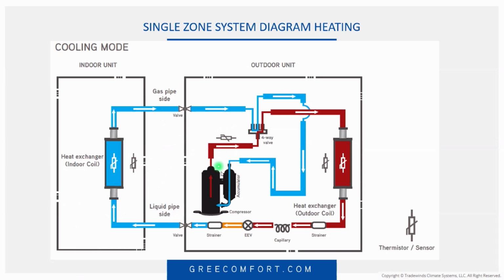That's one thing I really like about GREE. GREE is consistent in that they use a 50K thermistor for the discharge pipe. They use 20K thermistors for coil, whether it be on the indoor coil or the outdoor coil. If it is measuring air temperature, whether it's inside or outside, those are going to be 15K thermistors. So that's the easy way to remember it. If it's measuring air temperature, it's 15K.